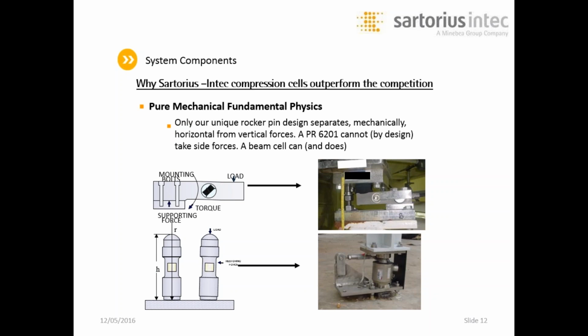The rigid mounting of the shear beam on top virtually assures that all torque forces will be transmitted to the load cell and interpreted incorrectly as weight values. Any movement, either horizontal, uplifting, or circular torque, will be sensed as erroneous weight values.